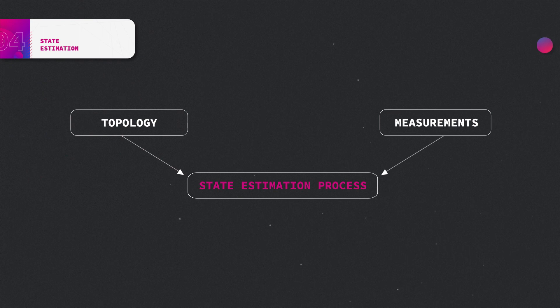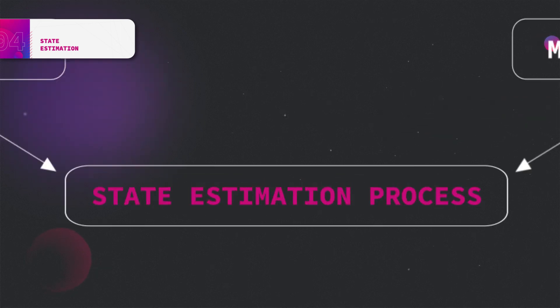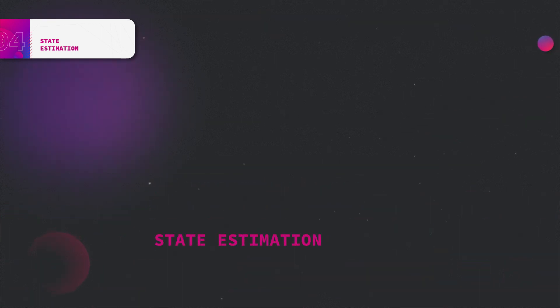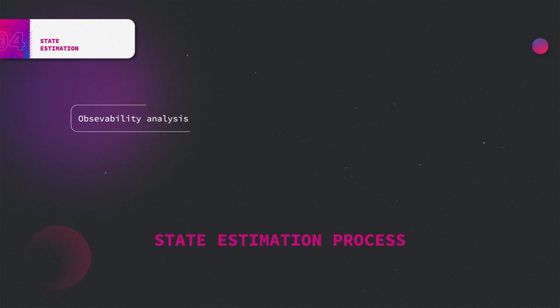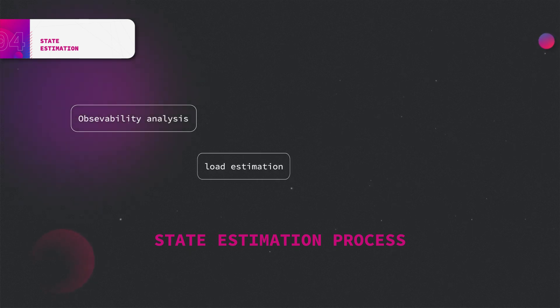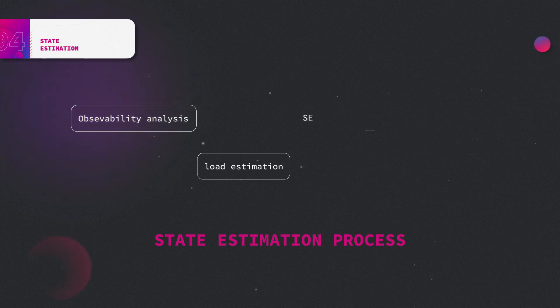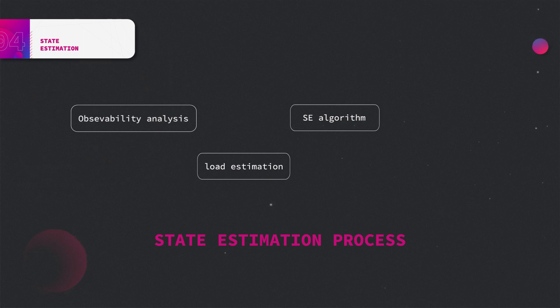The third part is the state estimation process itself. It consists of a number of underlying functionalities which can be summarized to the following groups. Through observability analysis, algorithm checks whether there are enough measurements available to estimate the network. And if not, load estimation functionality provides additional pseudo measurements to render the system observable. Then the system is being estimated by the means of chosen state estimation algorithm. And in the end, the results are being analyzed for the presence of errors.